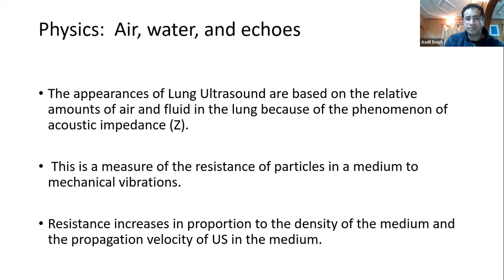This is a measure of the resistance of particles in a medium to mechanical vibrations. Resistance increases in proportion to the density of the medium and the propagation velocity of the ultrasound in the medium. When the ultrasound hits a relatively large and flat boundary between media with different impedances, some of the sound is transmitted across the boundary and some is reflected as an echo. The greater the difference in acoustic impedance, the greater the reflection.